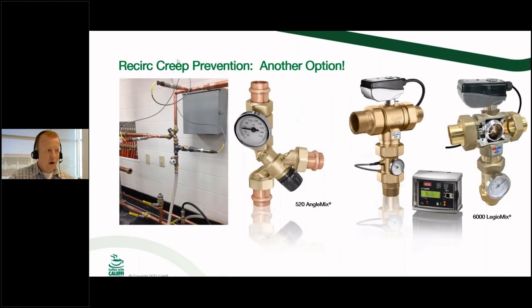So there is one other option though. There are actually a couple of mixing valves, and some of which that we actually create, that do have the ability to completely close off that hot inlet to prevent recirc creep. Okay, one of which is our AHR award-winning Angle Mix here. This uses a very interesting cartridge technology that's very fast reacting, and again, it does have the ability to completely close off that hot inlet. And you'll notice that the hot inlet and the mixed outlet are right in line with each other, so it makes piping really, really easy.